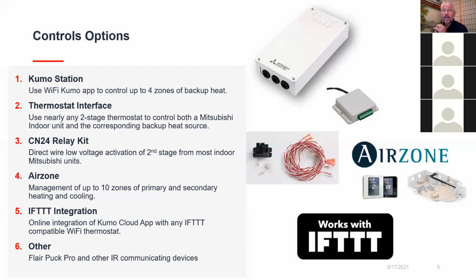Okay, fourth item is AirZone. AirZone is a third-party control, a suite of products that have the ability to communicate with different manufacturer systems. We have our little communicator board series that plugs into and is sold as a Mitsubishi product with AirZone. I think it was primarily introduced as an option for controls with Mitsubishi to allow for dampered ducts to be able to control ducted zones, and it does that very, very well. You can control up to 10 zones, whether they're ducted or dampers or radiant heat. It can manage all different kinds of heat sources.